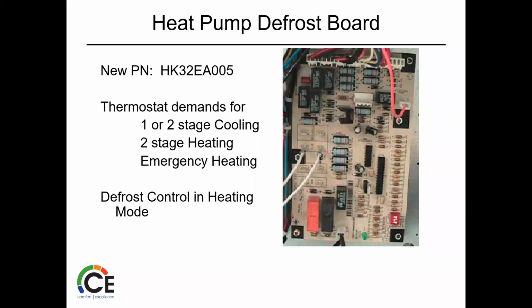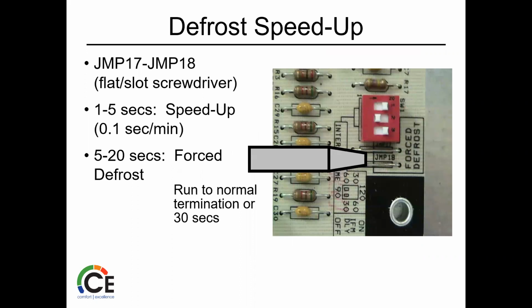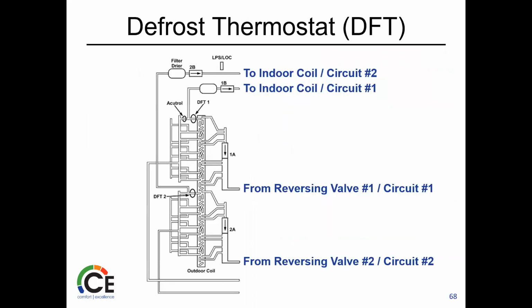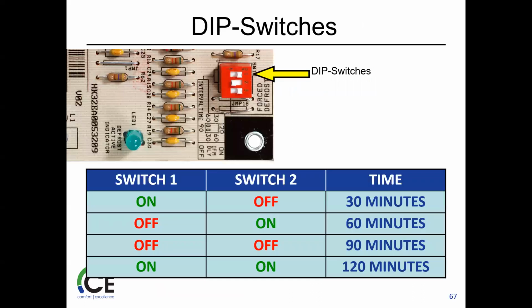So just kind of showing a few boards here. HK32EA005: thermostat demands, first, second stage cooling, second stage heat, emergency heating, defrost controls in heating mode. So most of the defrost boards do have a forced defrost on them. Some of the really new stuff doesn't, but most of them have that. So you'll see that same basic thing, right? We got the pins. You got a defrost thermostat or a thermistor somewhere that's monitoring temperature, telling it when to do it. Same basic operation as the residential units, depending on what your pins are set for.